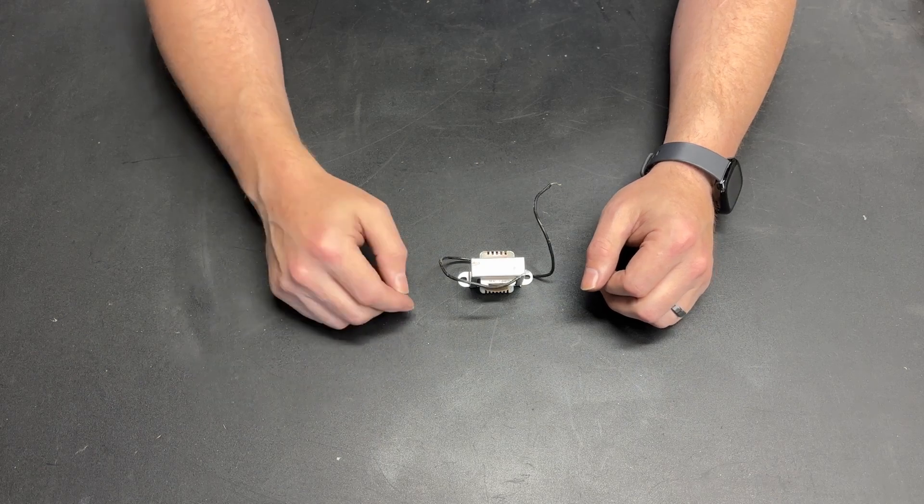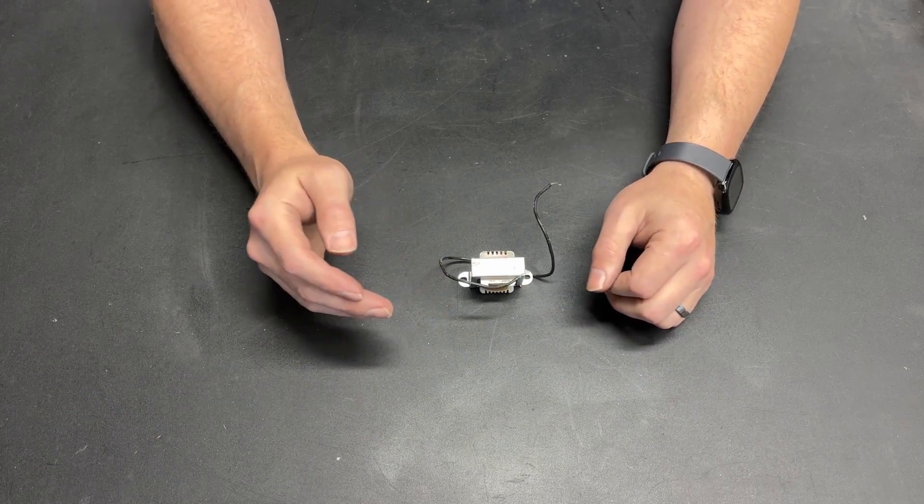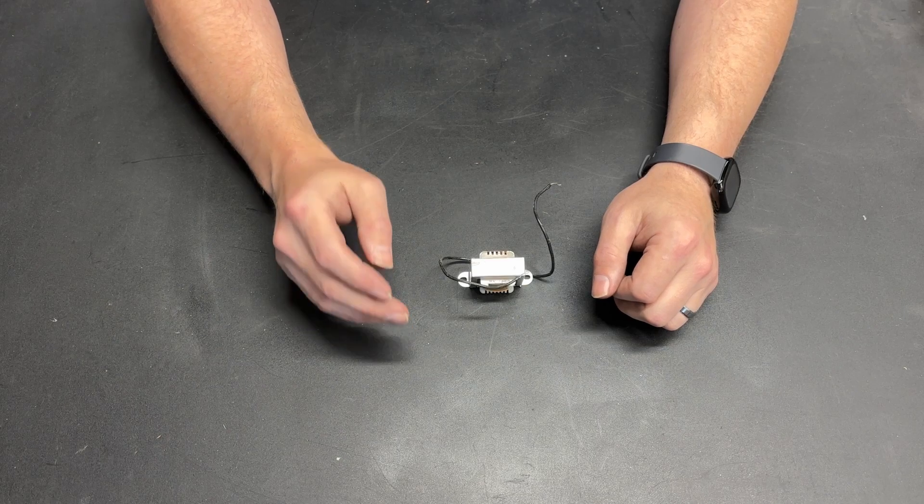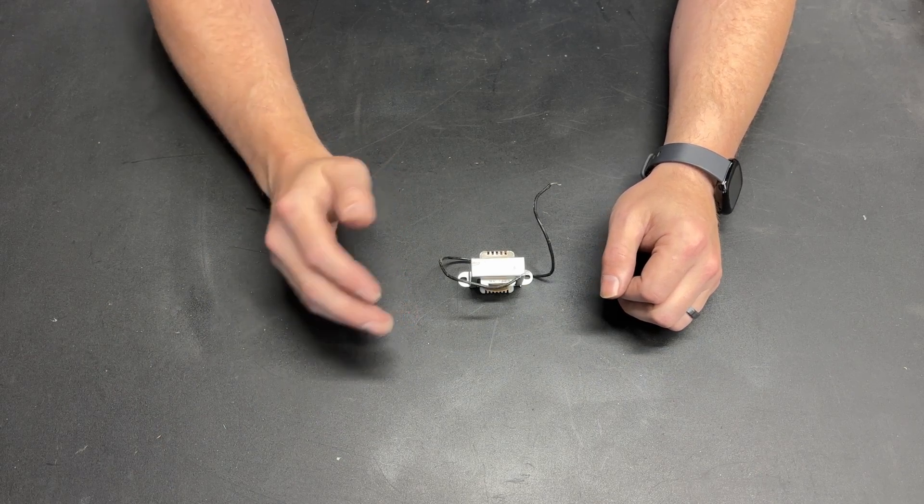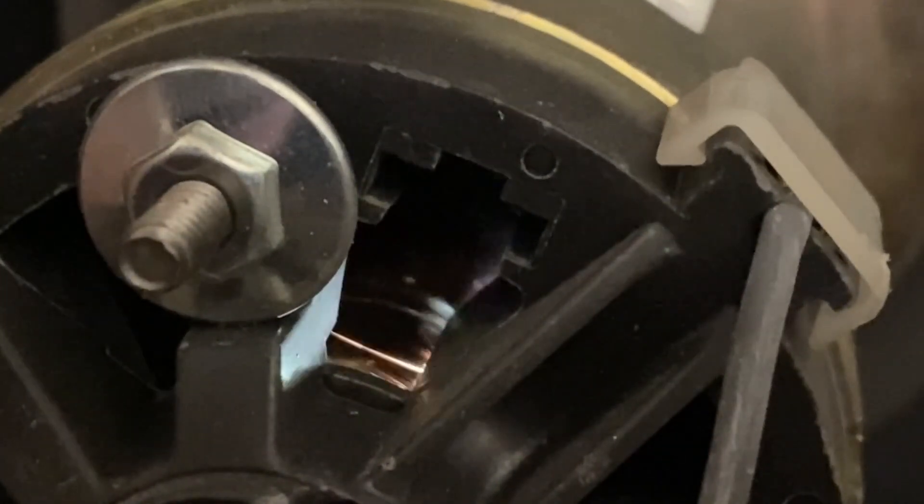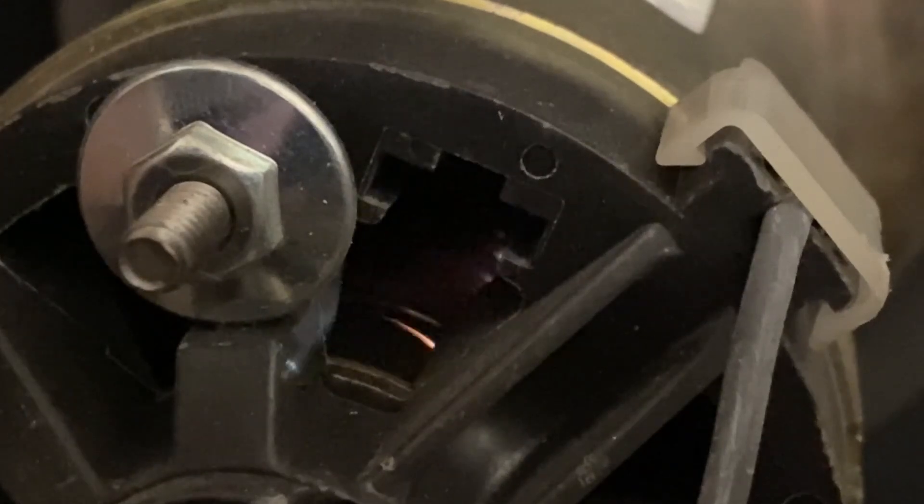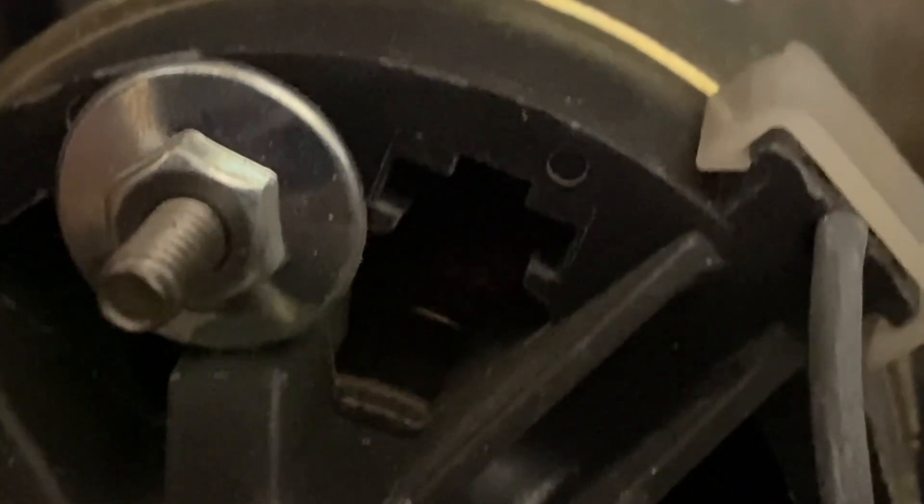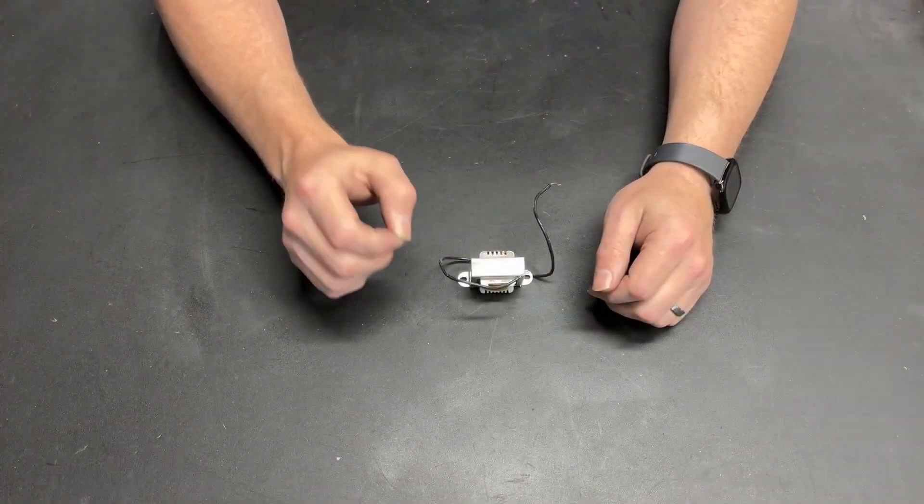So, I've done several videos showing the efficacy of a motor choke. If you look into the back of the motor where the brushes are making contact, you will see significant sparks if you are running an SCR-type power supply without a choke. You will see a significant reduction in sparks if you run the choke.